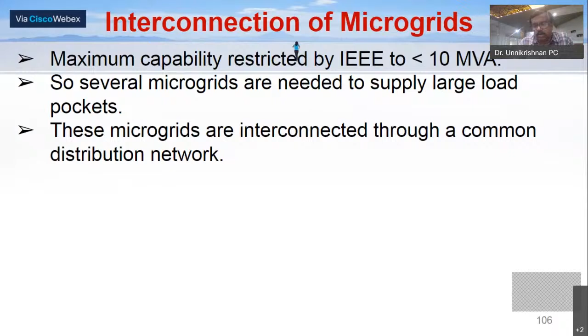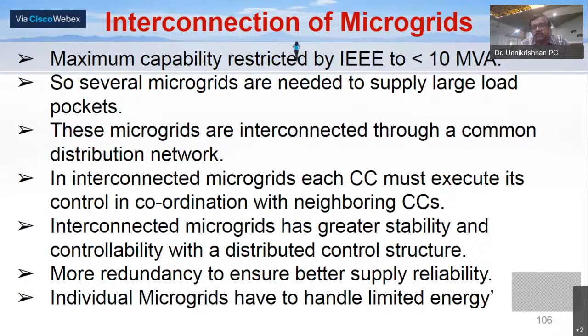Remember, each microgrid will have its own central controller, which will execute its control in coordination with the central controllers of the nearby microgrids. The basic advantage is that whenever you have excess and somebody else has less generation, you can share your resources. That is the basic idea. You can cater to higher load pockets by interconnecting the microgrids. Interconnected microgrids have greater stability and greater controllability, with a distributed control architecture, and redundancy. If some distributed generators fail, we can always get energy from the nearby microgrids. Also, the individual microgrids have to handle a limited energy, so the distributed generators can relax for some time.